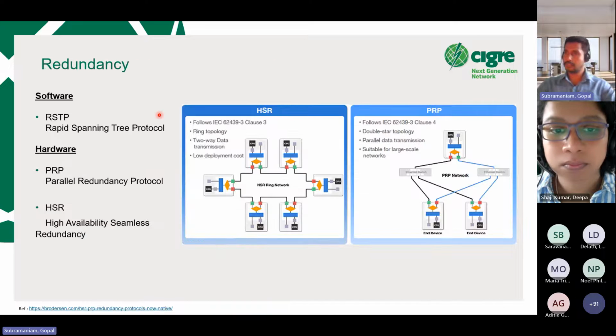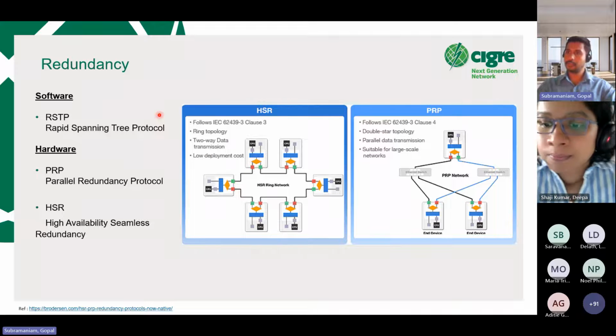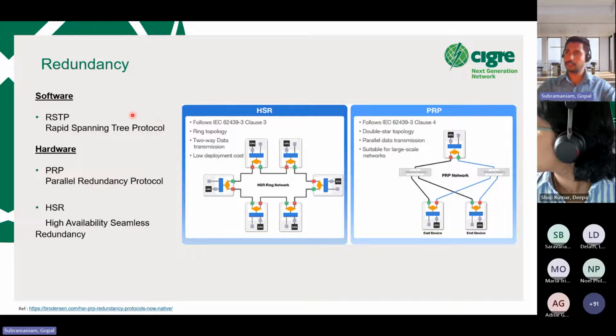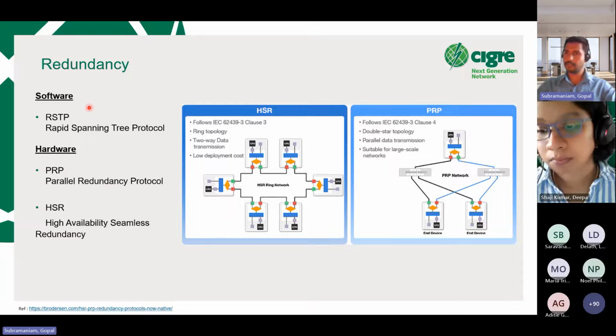And coming to redundancy, it can be implemented in two different types: software based redundancy and hardware based redundancy. Software based redundancy is generally existent everywhere, RSTP, rapid spanning tree protocol. One of the disadvantages is that there is a switch over time whenever a ring fails. There is some time delay to switch over from one network to the other network. So to overcome that, we have two hardware-based redundancy protocols: parallel redundancy protocol and high availability seamless redundancy.